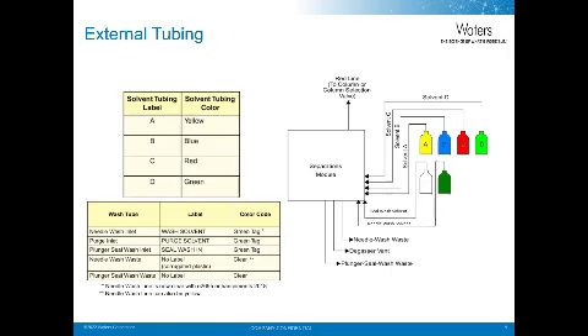This explains the various solvent lines and the tubing associated with them. If the solvent lines are not labeled while going to the customer site, and you must remove more than one at a time, make sure to tape them and label them so you don't lose track of which one is which. Next, the mobile phases enter the degasser tray. The purpose of the degasser is to remove any gases from the solvent.